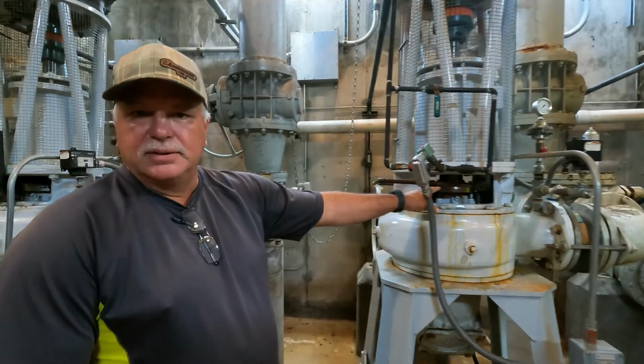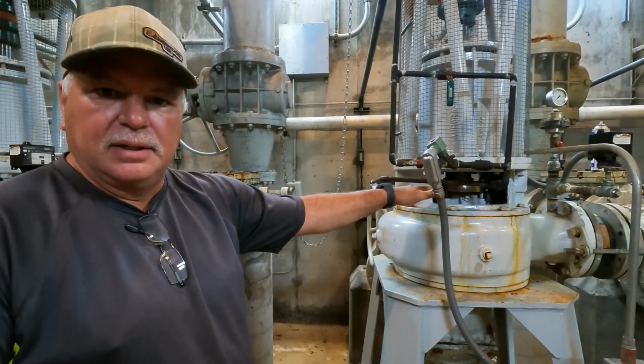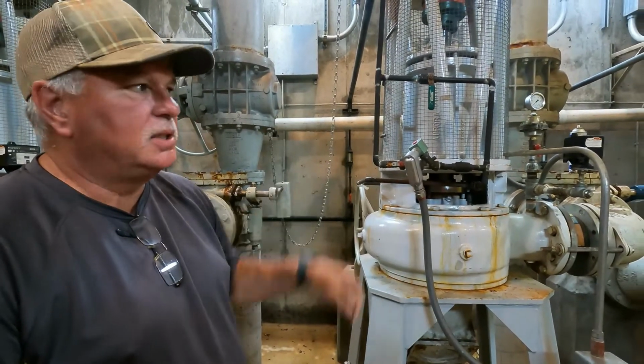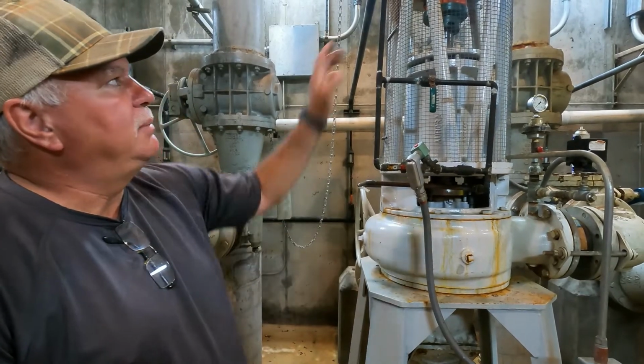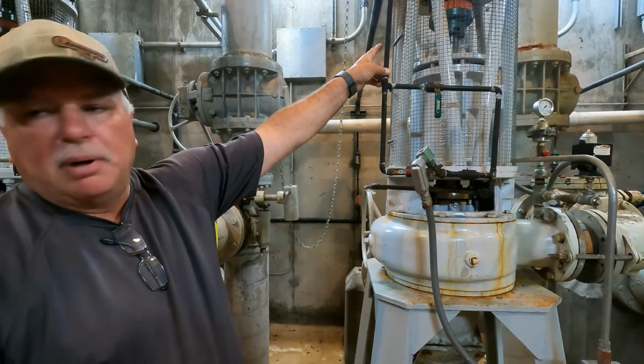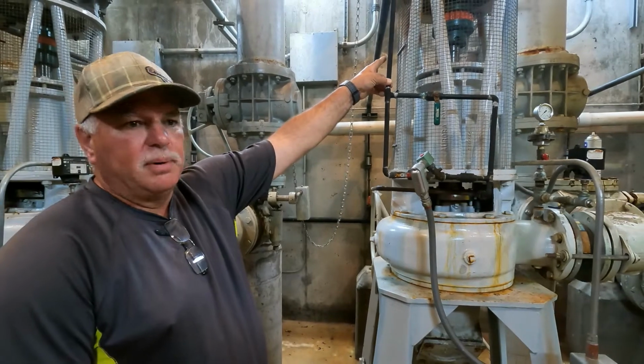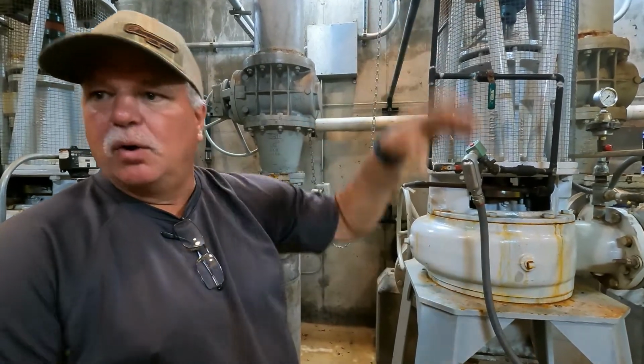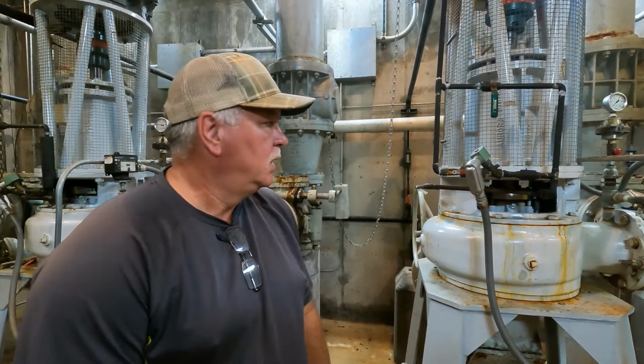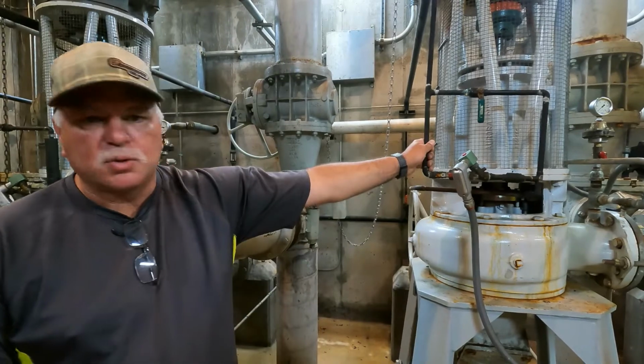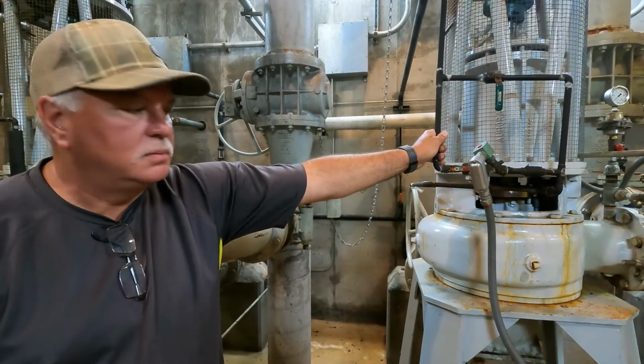Got mechanical seals in them. There's no stuffing, no packing in the stuffing box. These are all mechanical seals in these pumps. We've got to keep track and keep up on the couplings that are between the motor and the pump as well. Different times if they get over torqued, they'll break, or just then wearing over time, they'll strip out and have to change those. We want to monitor the wash water that goes into the mechanical seal.